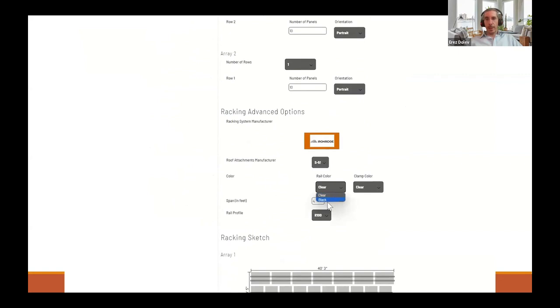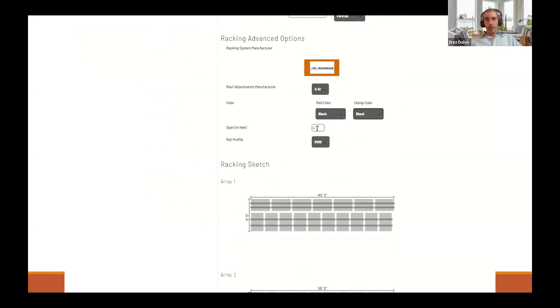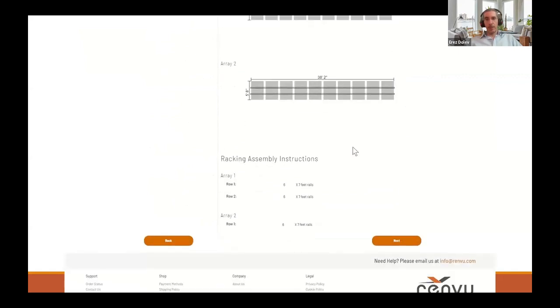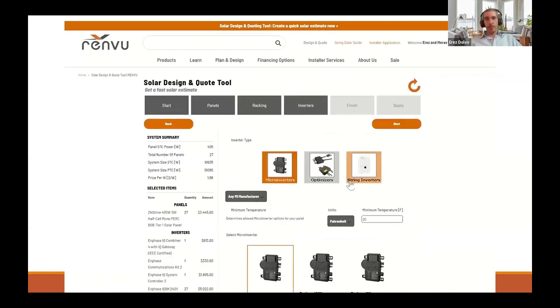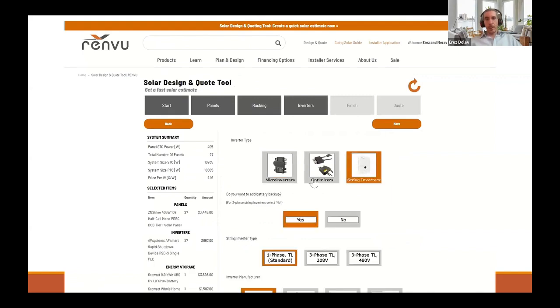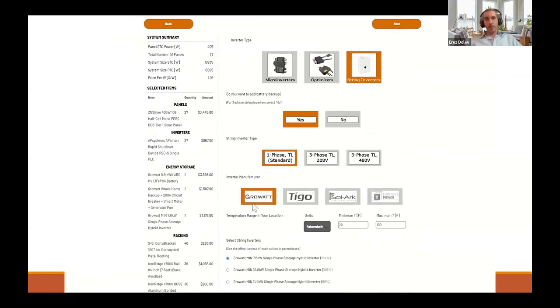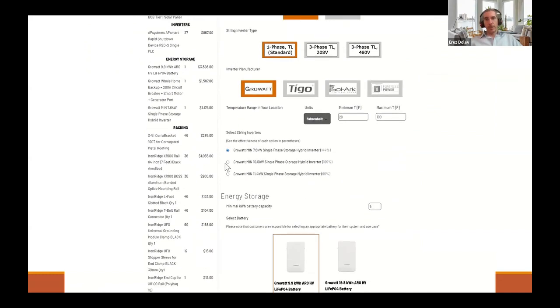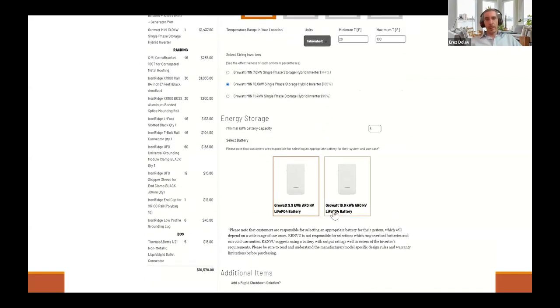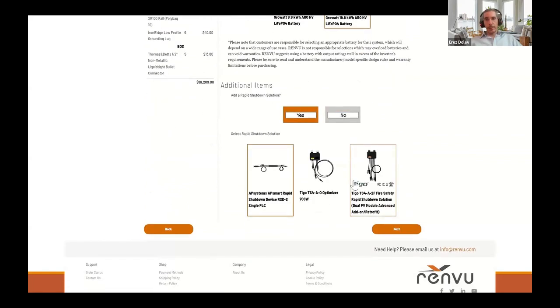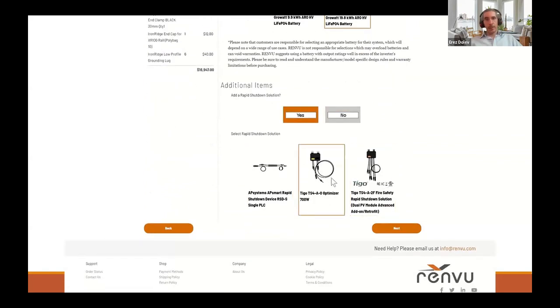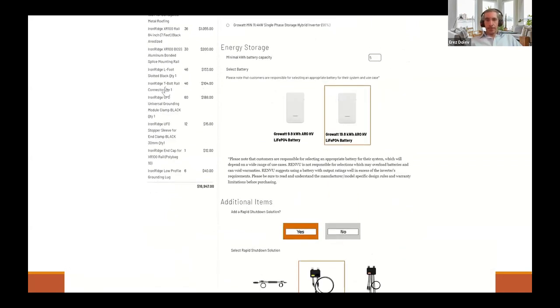I changed to black rails, black clamps, and changed the span here to 6 feet. The system creates a sketch of the array with dimensions, so you can verify that this design fits the space you have. Then choose your inverter type from microinverters, optimizers, and string inverters. I selected string inverters here, and for storage options, I'll select single phase and Growatt. I'll select the MIN 10K and the 19.8 ARO battery.